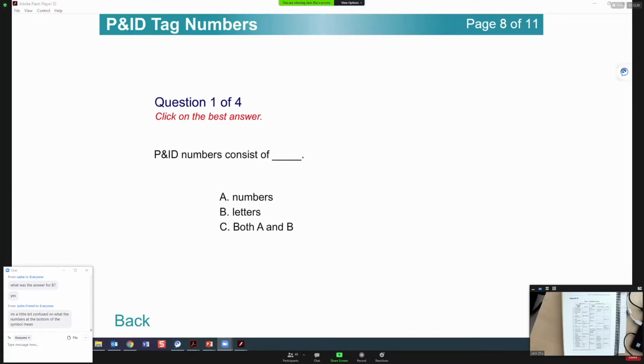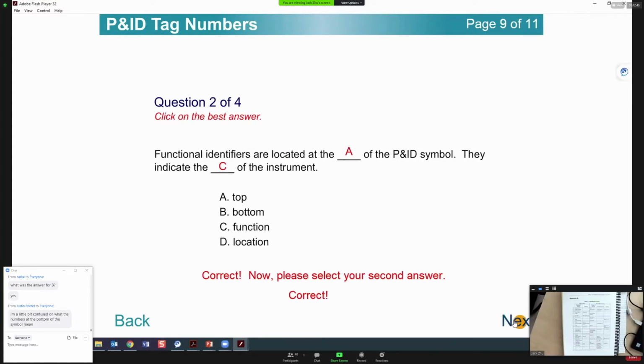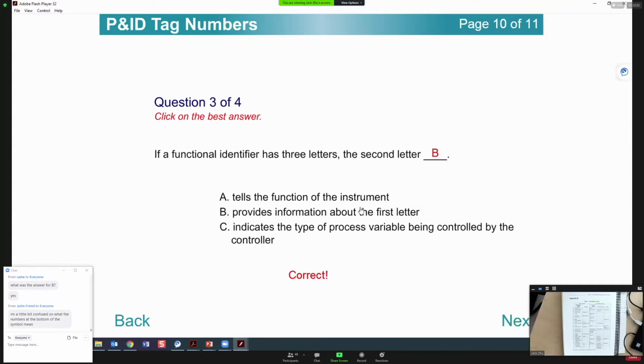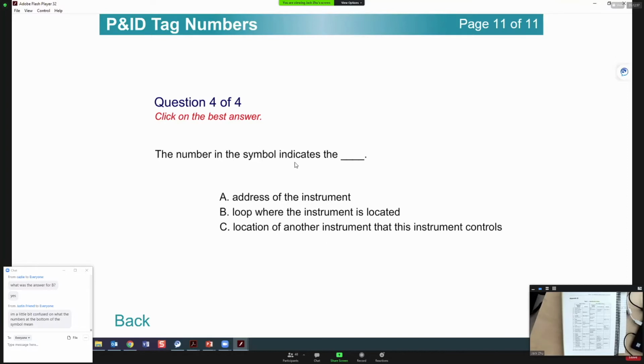A little bit confused on what the number at the bottom is. Oh, okay. So we did this. Don't need to worry about this. The number in the symbol indicates the loop where the instrument is located. So you might have a different instrument, right? You could have a complex control. You might have, let's say, a temperature sensor. You will have several temperature sensors, but depending on those numbers at the bottom, they will tell you this temperature sensor is in which control loop and where it's going to be located. Yeah, you can think about a loop as a circuit or a branch of a circuit.